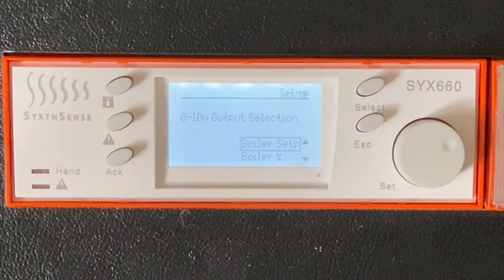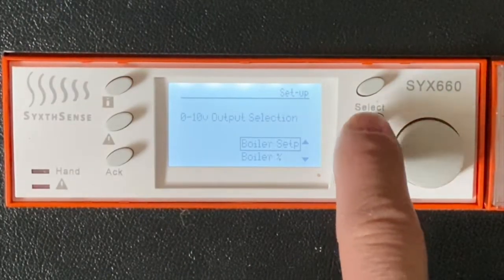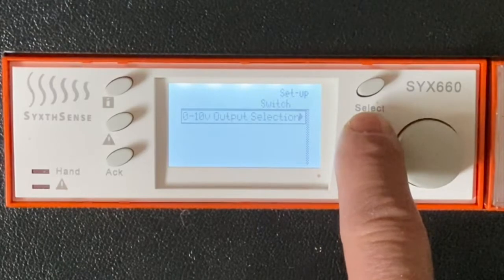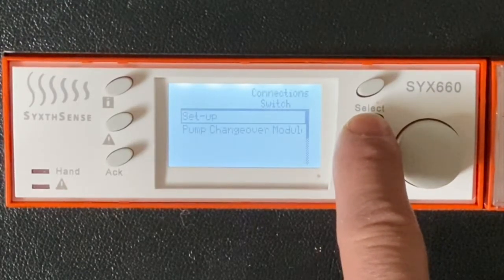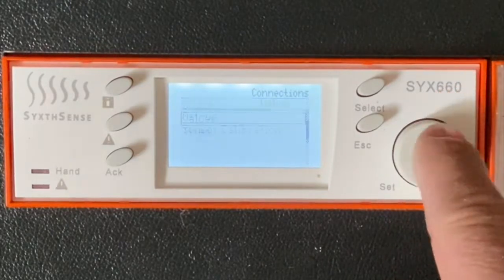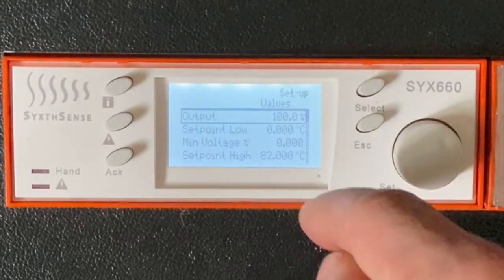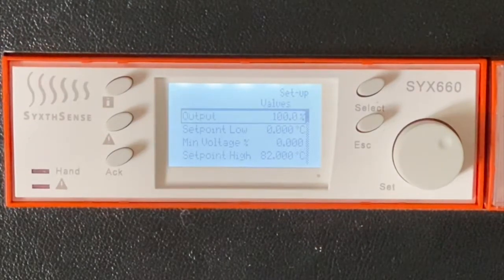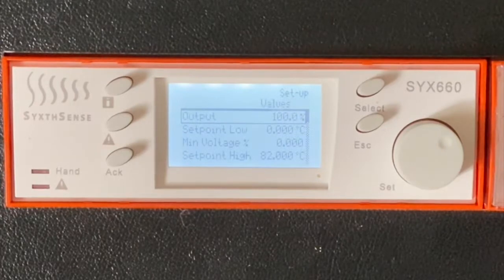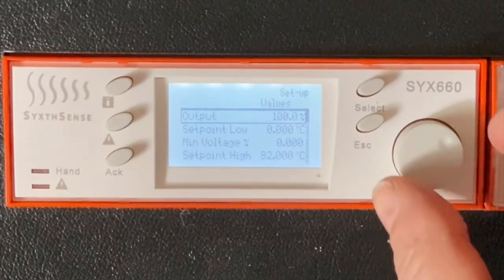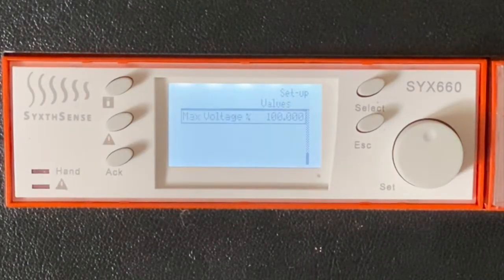So if we do choose boiler set point, we do need to be able to scale the output, and that's what we do in the values section in the setup menu. So we choose escape, escape, escape, this time choose setup, and this time we choose values, and this is where we can scale the output. Where it says output, that's the current voltage reading. Set point low and the minimum voltage go hand in hand. This is where we set the expected set point minimum for the relevant voltage, and we also set the set point high with its relevant voltage. In terms of percentage, 100% would be 10 volts, 0% would be 0 volts.